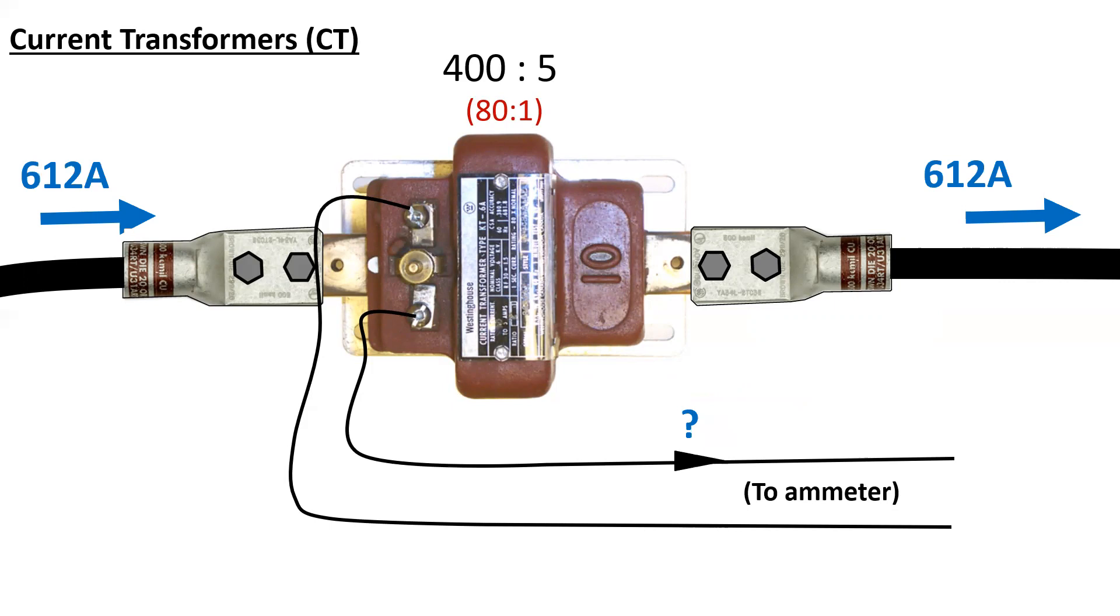Let's say I had 612 amps instead, 612 amps flowing through, same CT, 80 to 1. How many amps would be flowing on the secondary to the ammeter? Well, again, we would take 612, divide it by 80, and we'd end up with 7.65 amps.